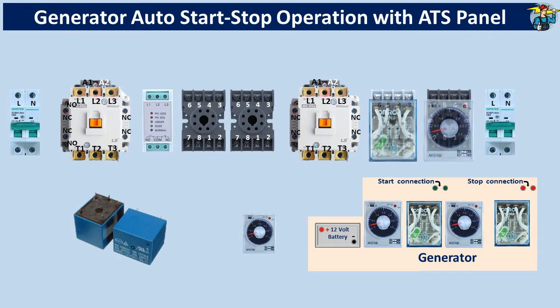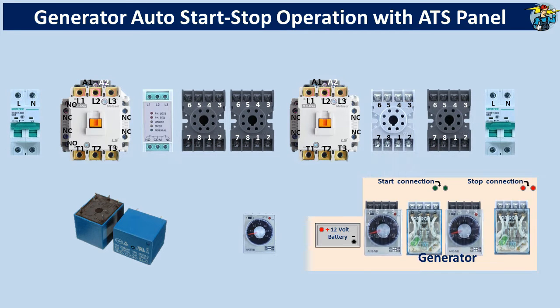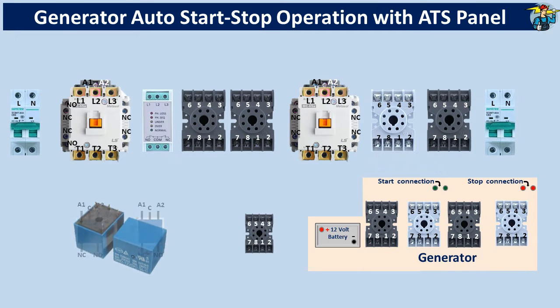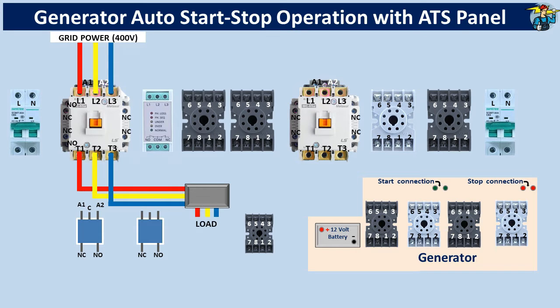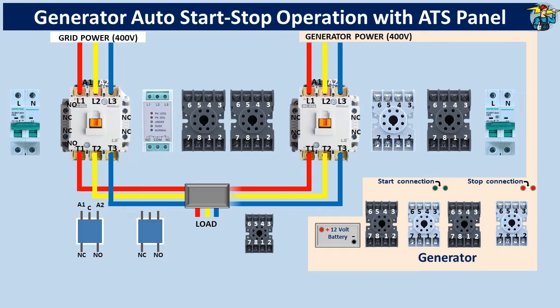Pulling the timers and relays out of their bases reveals the numbered terminals. 3-phase 400V power lines from the mains are connected through the contactor to the load. 3 generator power connection lines are also connected to the load through the other magnetic contactor. Now, connect 3-phase lines of the grid to the phase failure relay.